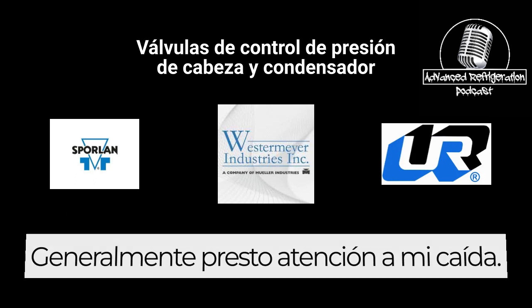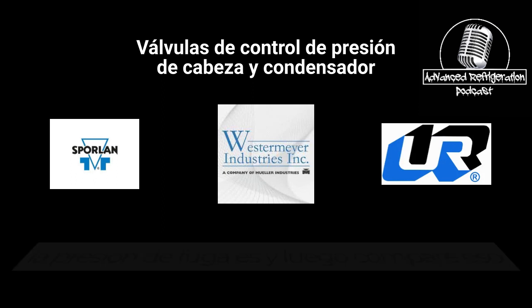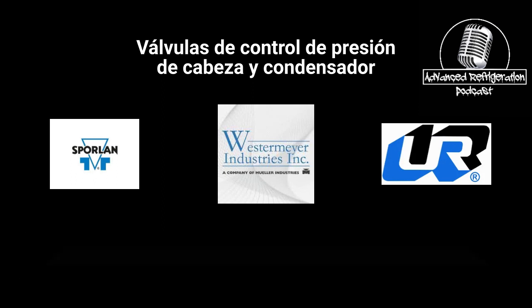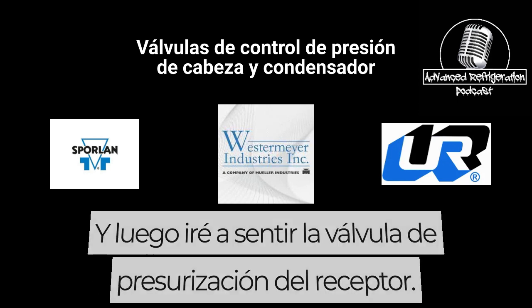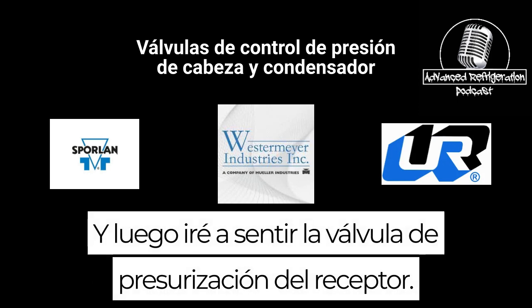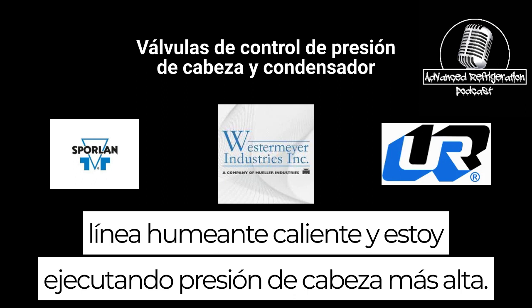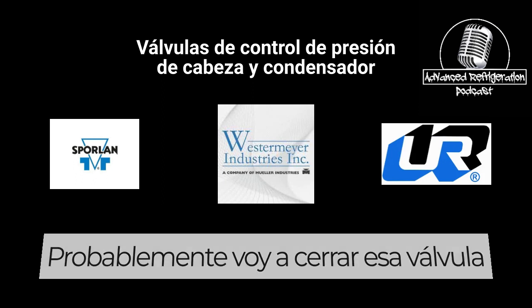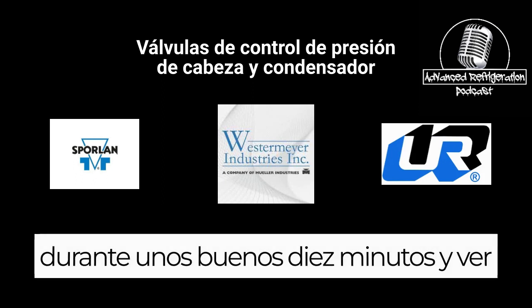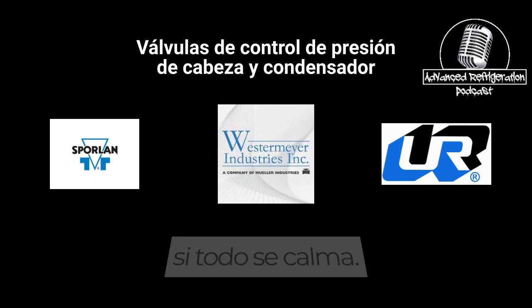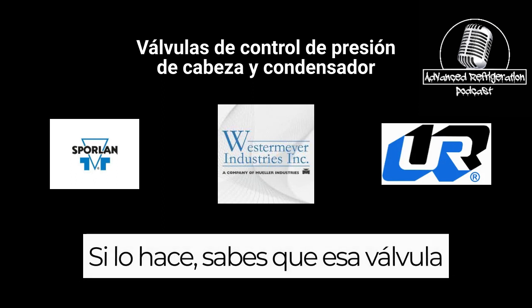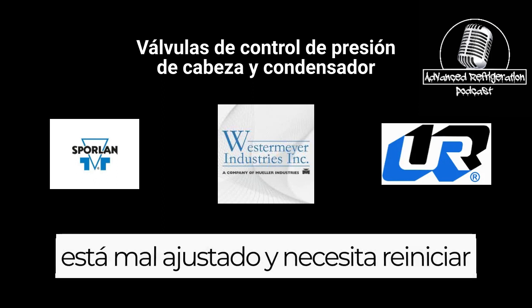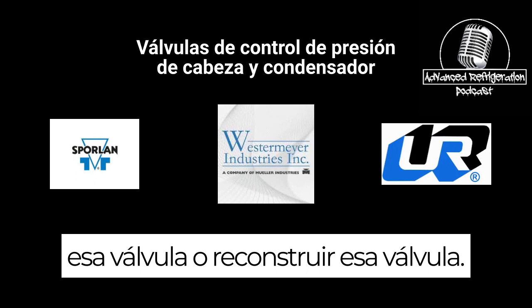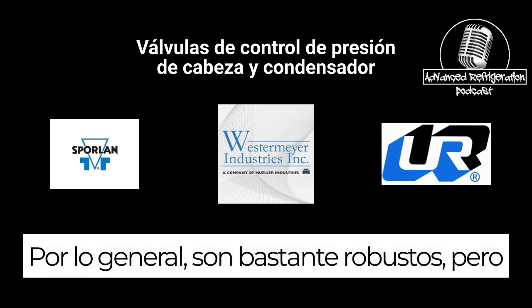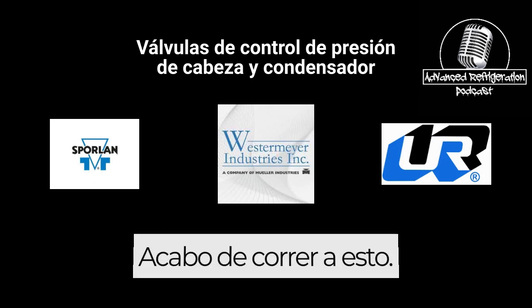So I generally pay attention to what my drop leg pressure is, and then compare that to what the valve setting should be. If I go feel the receiver pressurization valve's line smoking hot and I'm running higher head pressure, I'm probably going to valve that valve off for a good 10 minute stint and see if everything calms down. If it does, that valve's improperly adjusted and you need to reset that valve or rebuild that valve. Typically they're pretty robust, but I just ran into this this week.